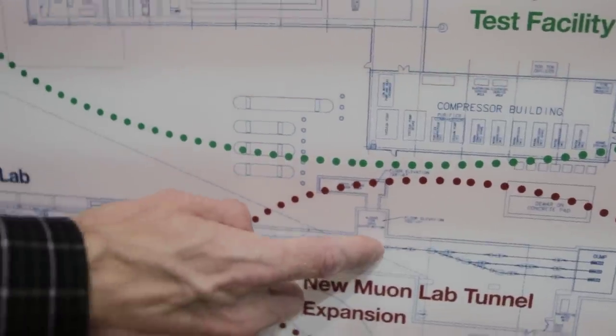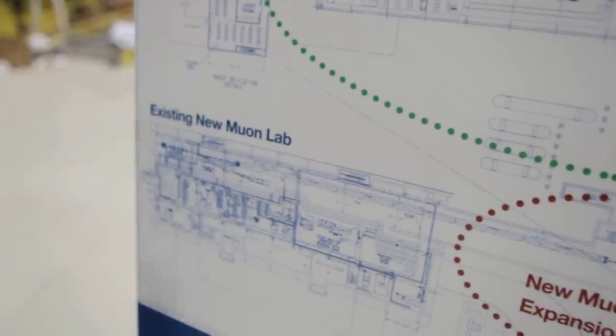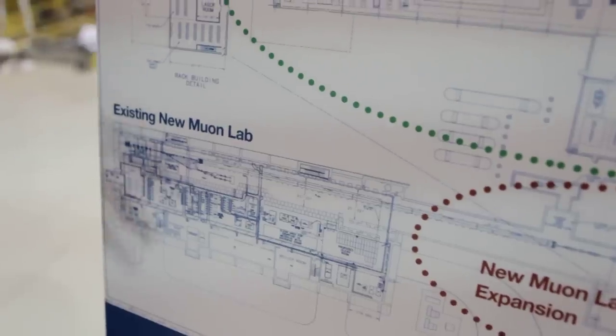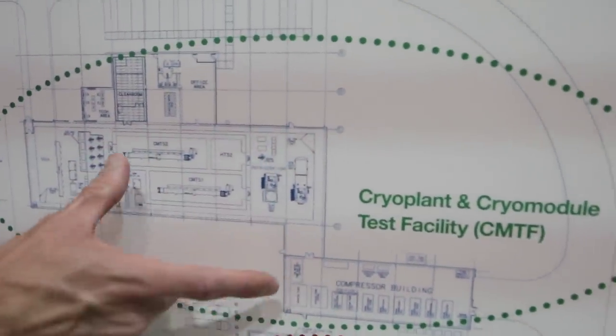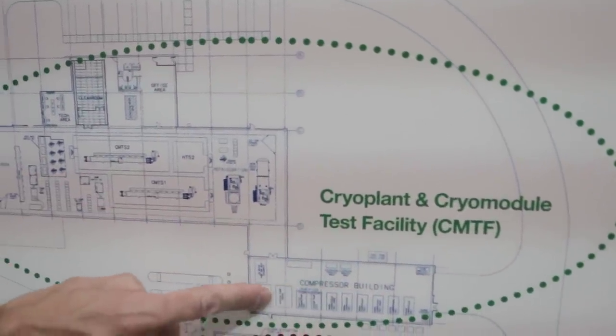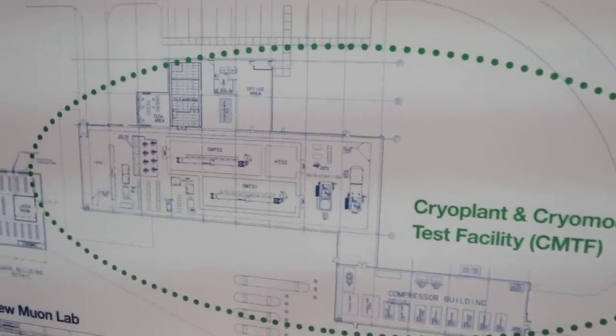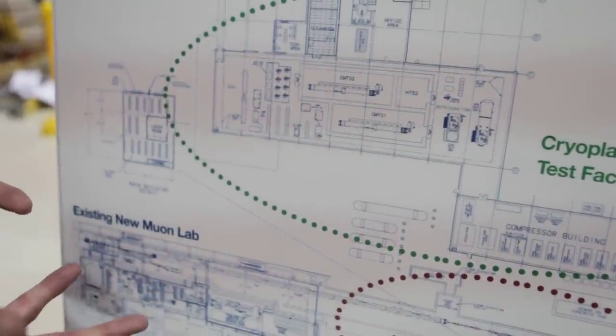Because we have a bigger accelerator, we need more cryogenic capacity. With the stimulus funds, we're also buying a cryogenic refrigerator — a helium refrigerator. That goes in these two new buildings: the refrigerator in one, and all the compressors and everything for it in the other. That'll feed into the tunnel and cool down the cryomodules, so we get our superconducting capability.